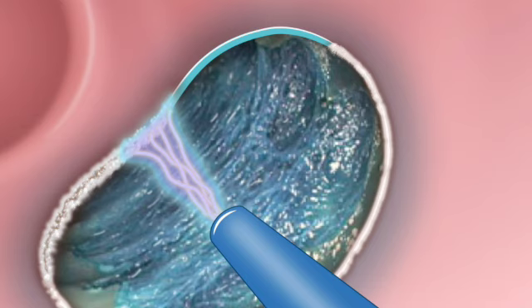Okay, so then there's the third mode, precise APC. In this setting, the generator actually micro-adjusts the power output based on exactly how close the catheter tip is to the mucosa. This is where the tech gets really impressive. It's essentially a smart nozzle that dynamically alters the pressure to guarantee the exact same impact, even if your hand is shaking or the distance changes. What's fascinating here is the biological necessity behind that specific mode. I mean, in a vacuum, holding a probe exactly 1 or 2 millimeters away from a target is simple. Sure, on a test bench.